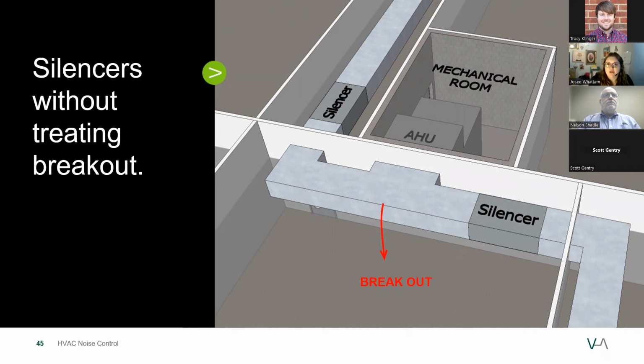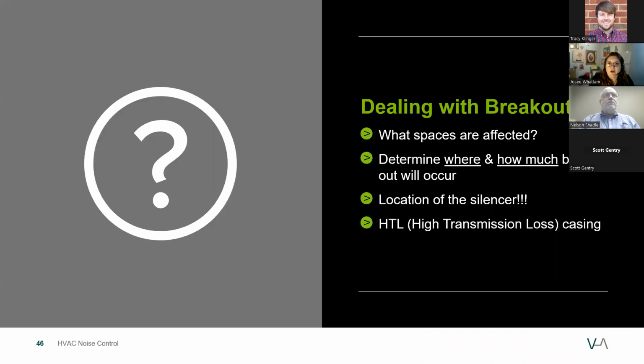From the time the duct enters the occupied space up to the outlet of the silencer, noise can break out of the ducting. Now, would this system have worked if the ductwork was lagged? It would, if you lagged all of the ductwork up to the silencers, but the cost of lagging this ductwork would be multiple times that of the silencers. So how would you deal with breakout in that example?